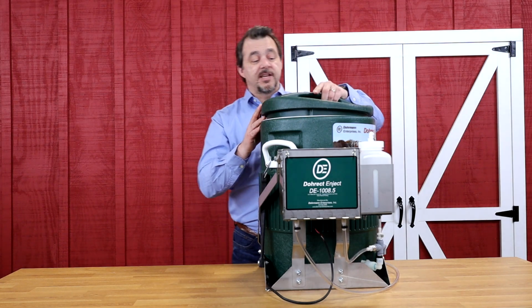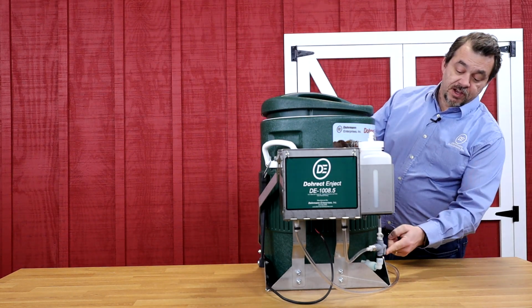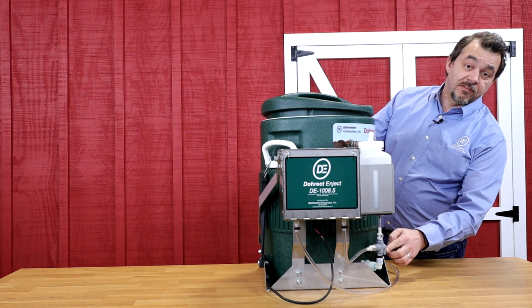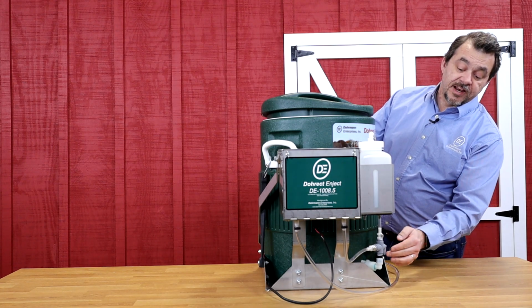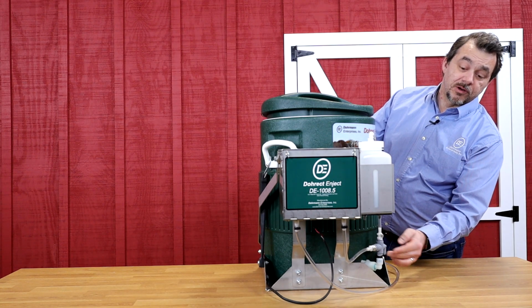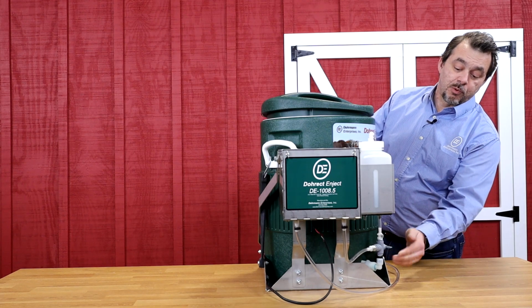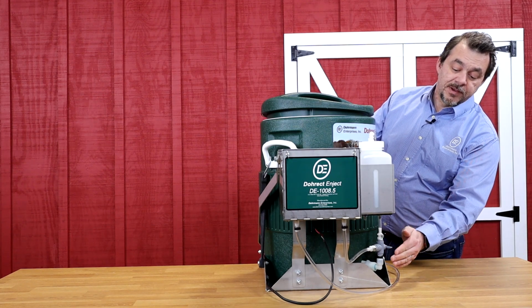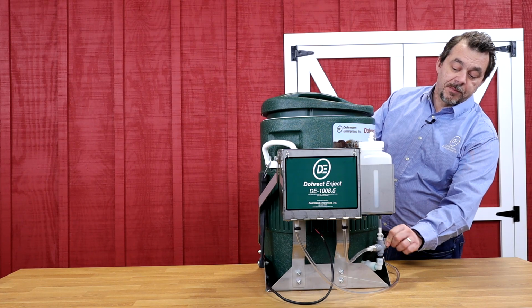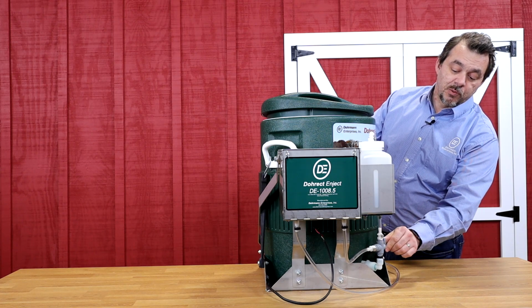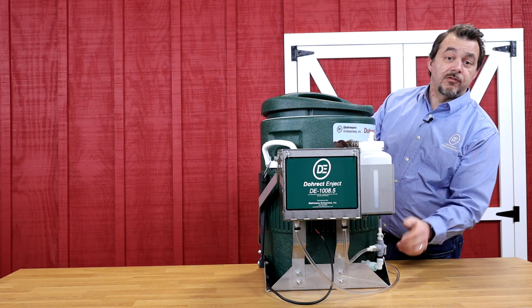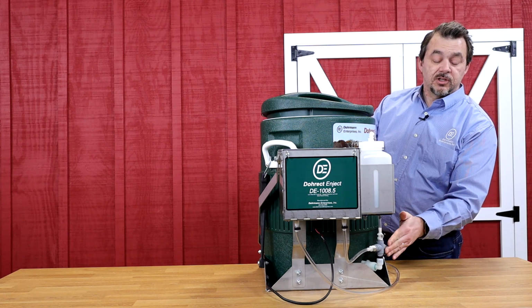And then the other thing we want to take a look at is this valve. We want to make sure that the handle on the valve is pointing down. That indicates that it's drawing from the cooler. If we have the valve handle either pointing out towards you, that will be a shutoff position, or up would be for your flush bottle. So we want to make sure that we're trying to draw from the fluid that's in the cooler. So let's make sure that that valve is pointed down.